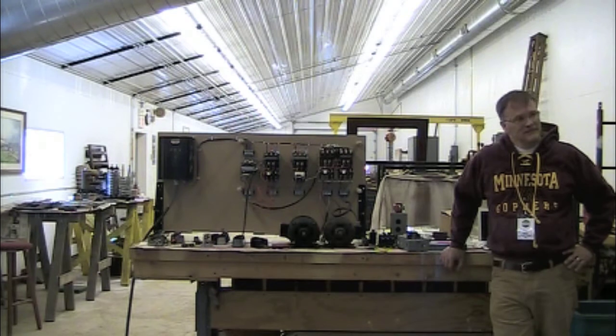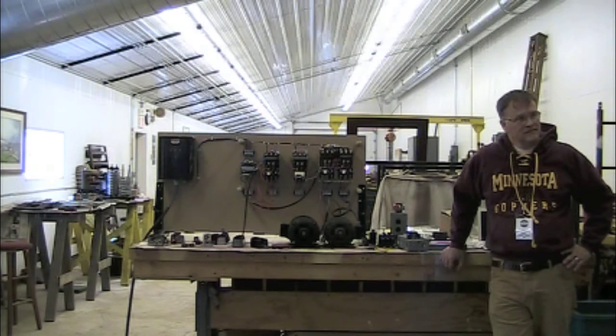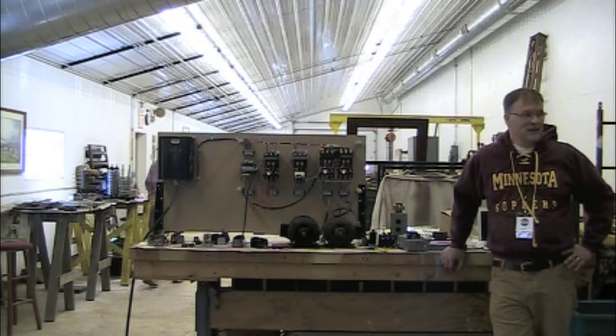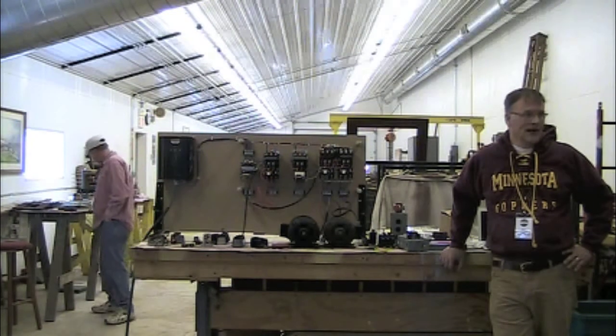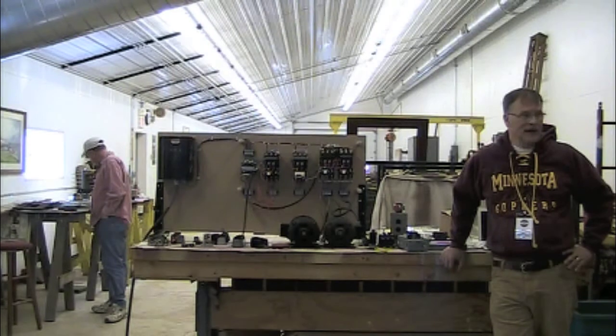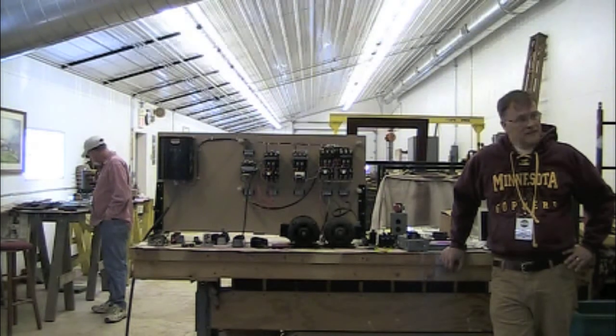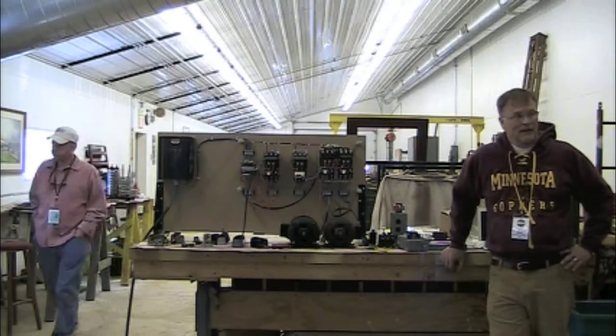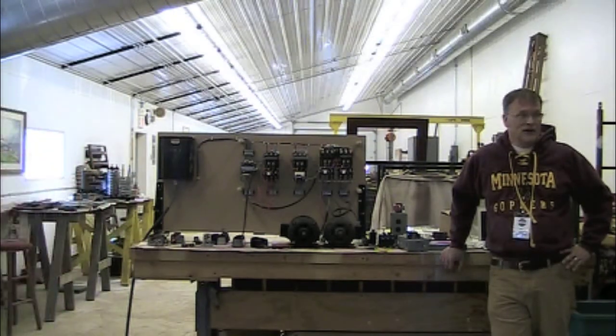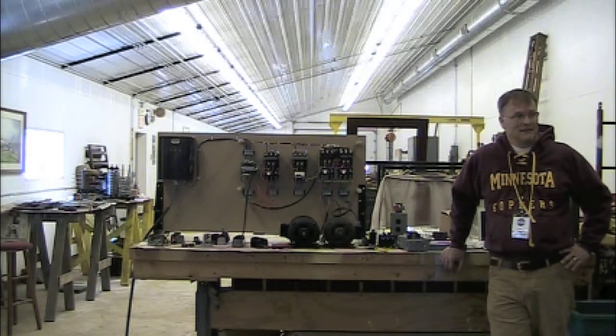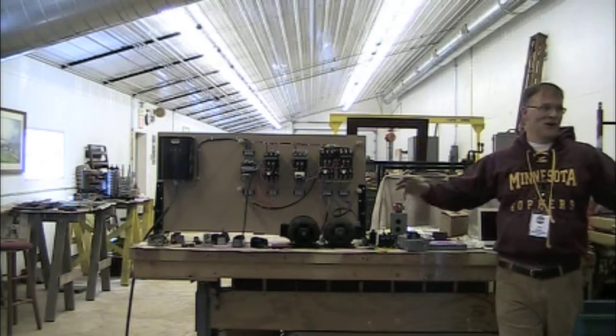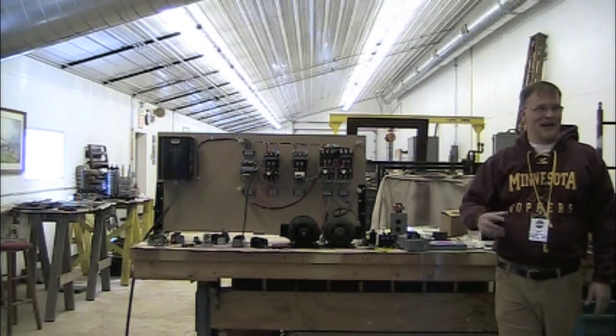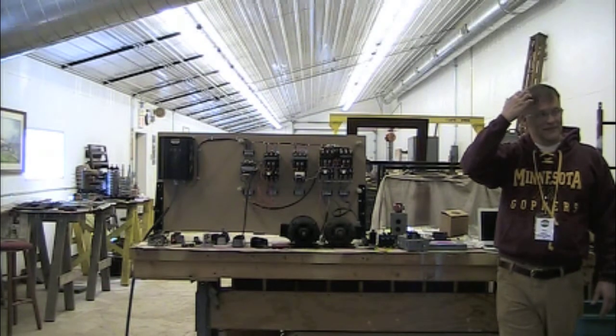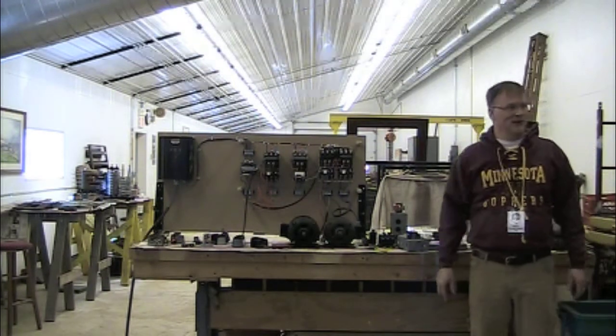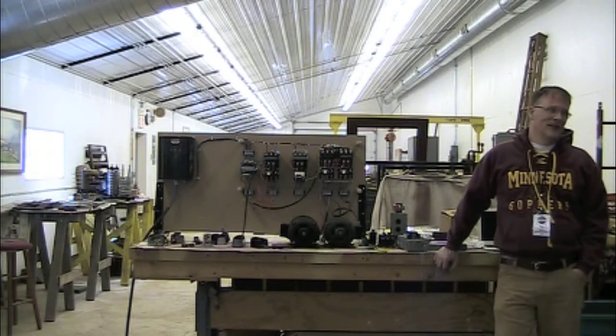So is it normal to ground your operator? Yeah, code-wise for everything, especially when you're running line voltage to it or higher, everything should have a ground path. Even though the secondary after the control transformer, well, on here, if the control circuit shorted to ground, it's not going to trip anything because there's no path. But there's no path to you either because it's not common coming through the electrical system. So you don't have a ground path back to it either. So that's a little different.